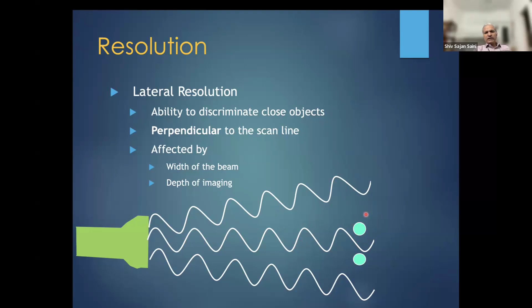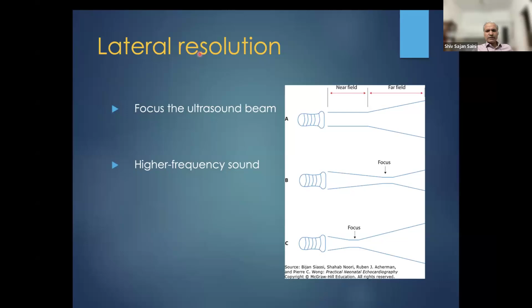So what is the way out? The way out is the focus. You have to use the focus of the ultrasound machine to optimize the lateral resolution. Once this probe throws the signal and it goes inside, instead of diverging directly, the machine asks the beams to converge to the focal point and then diverge. So you can use the focus near and far depending upon your anatomical area of interest. If your area of interest is, say, like this, you can adjust the focus up and down accordingly. We'll shortly see how to adjust the focus. And second, the higher the frequency, the better the lateral resolution, and the narrower the sector, the better the lateral resolution. So basically, these are the three ways to improve the lateral resolution.